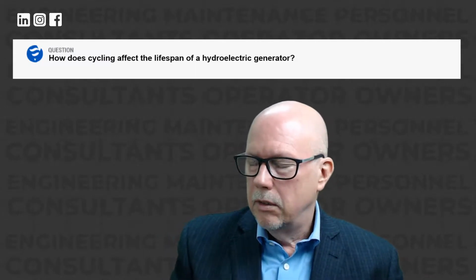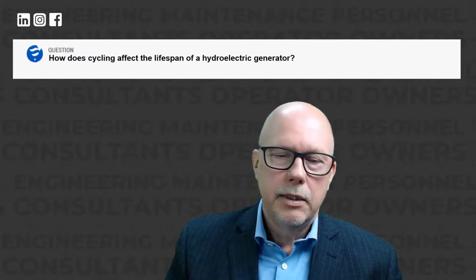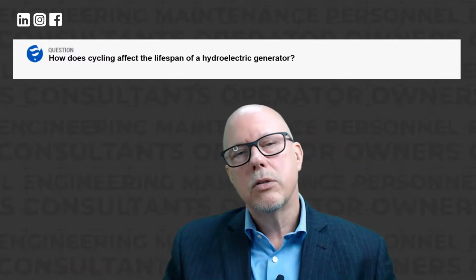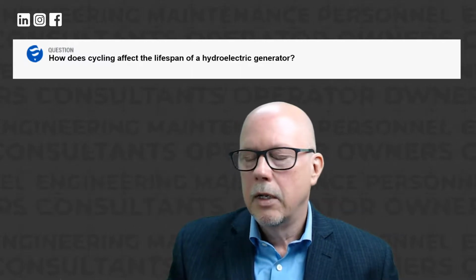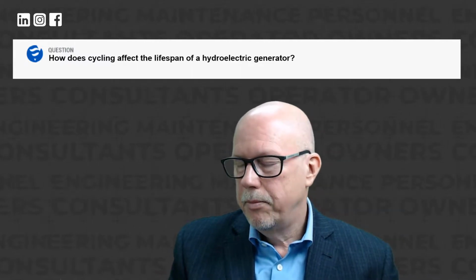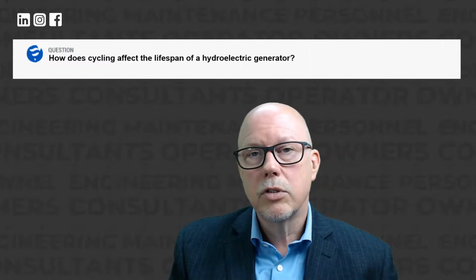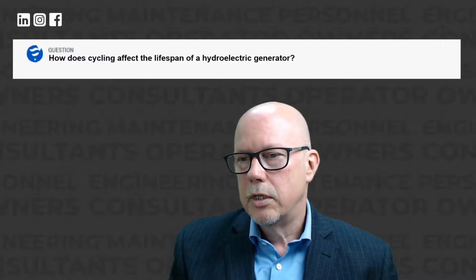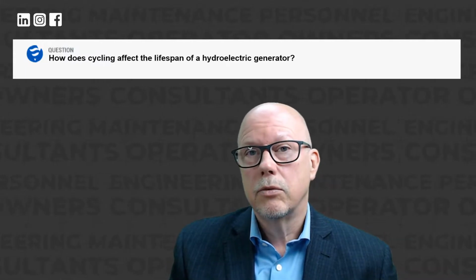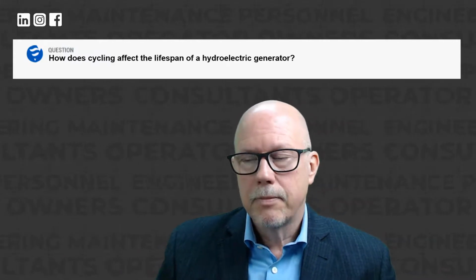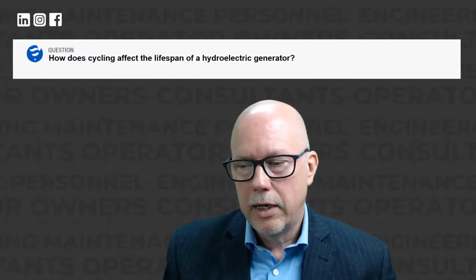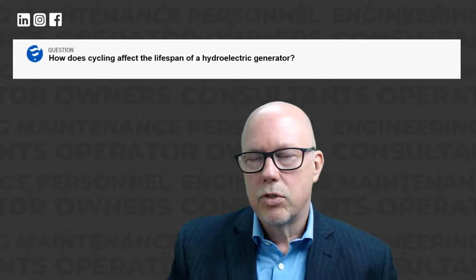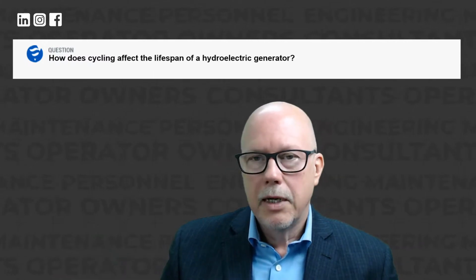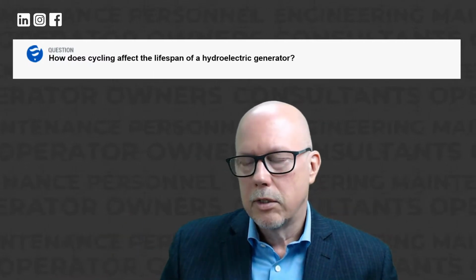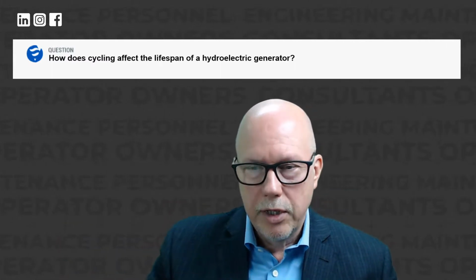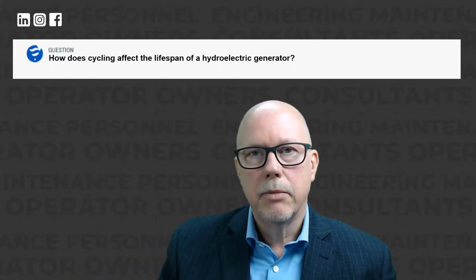It's also been said that the changing of heat causes insulation wear and tear. I've seen a paper discussing that the most damage to insulation comes from prolonged exposure to heat. Therefore, base load units will have insulation that wears out faster than units that cycle. The idea is that what deteriorates the insulation is prolonged exposure to heat, which chemically alters the epoxy mica.